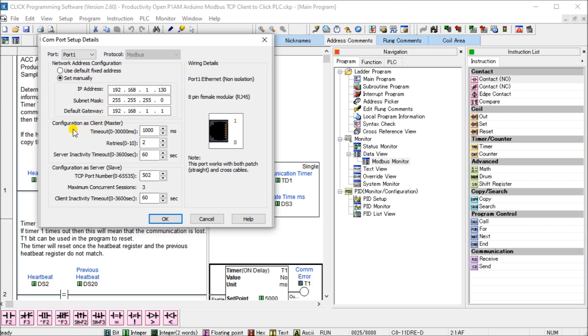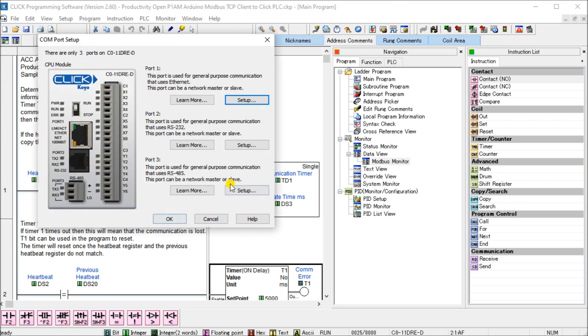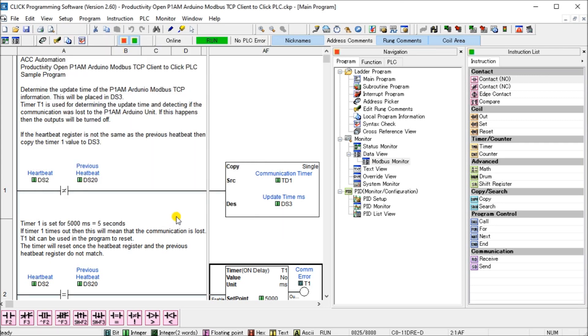Then we have our configuration for our client or master which we're not using in this case. We're going to configure for our server or slave on our Modbus network and we'll see that we have the TCP port number will be 502 which is default for Modbus TCP or Modbus Ethernet. Our maximum concurrent sessions is three and we have a timeout of 60 seconds.